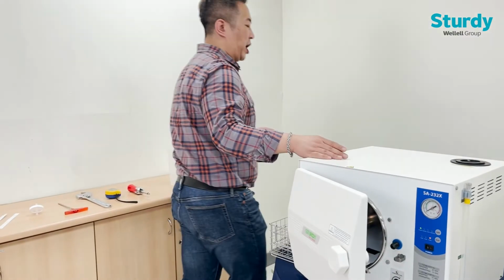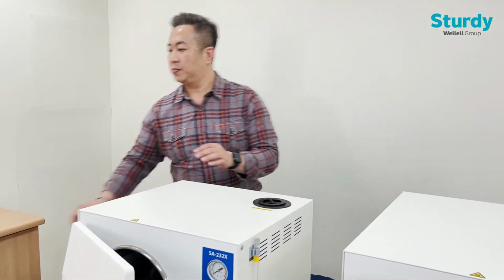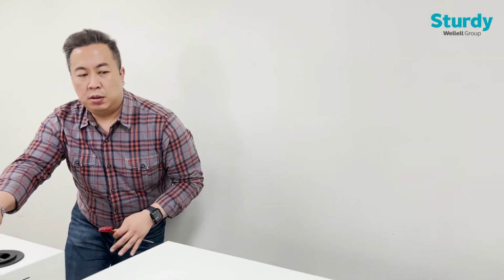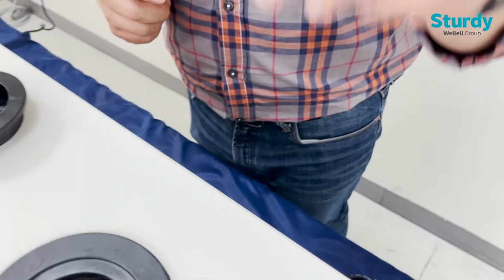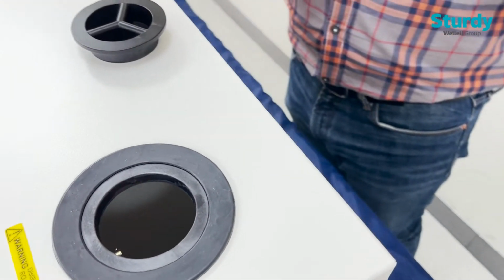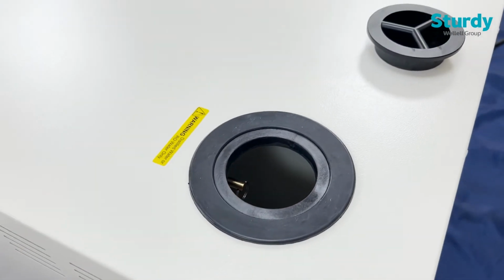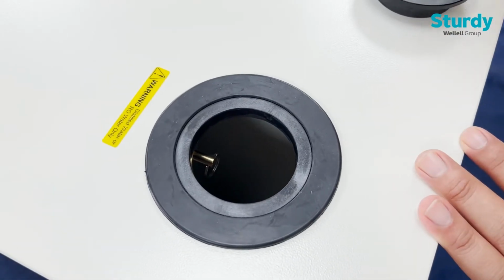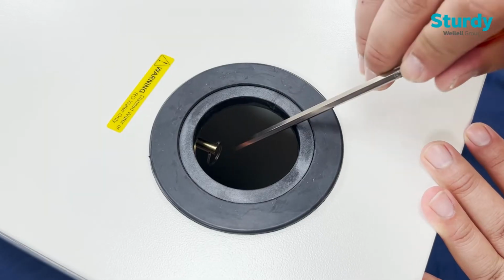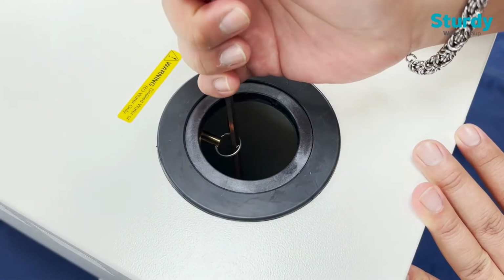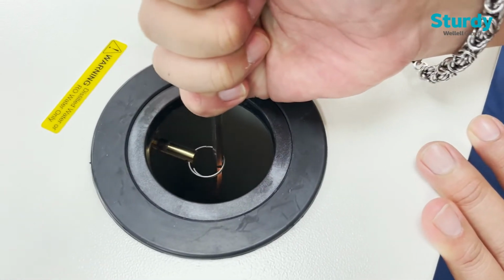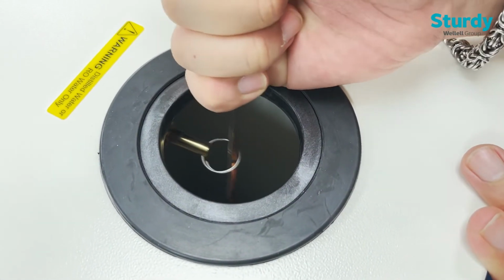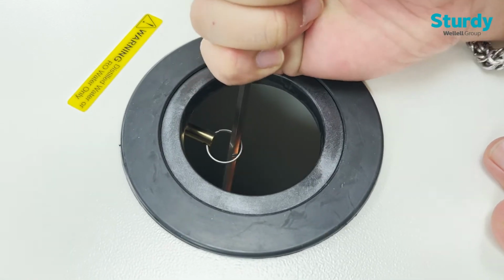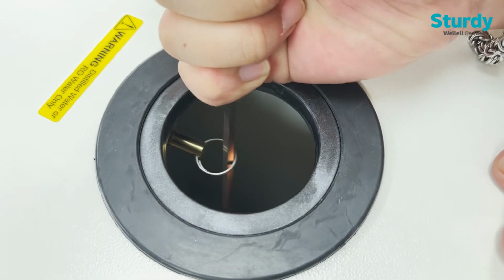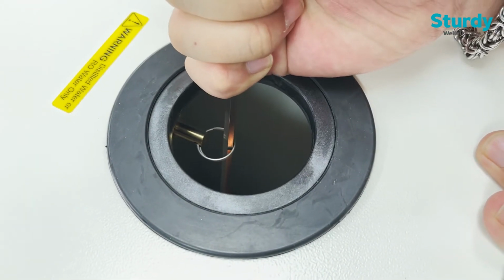Also, we need to check the safety valve. Checking the safety valve is most important, and we can find it inside the water tank. The purpose of the safety valve is to release pressure overload and overheating. To inspect it, using an instrument, simply pull the safety valve outward to see if it's stuck or not. If it's not stuck, that means the safety valve is 100%. In case the safety valve cannot be pulled out, it's recommended to be replaced.